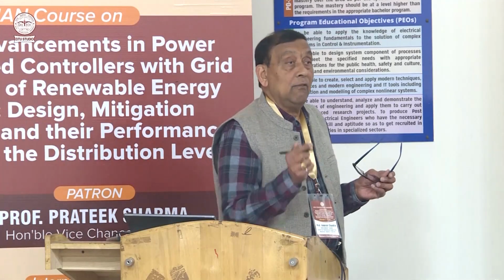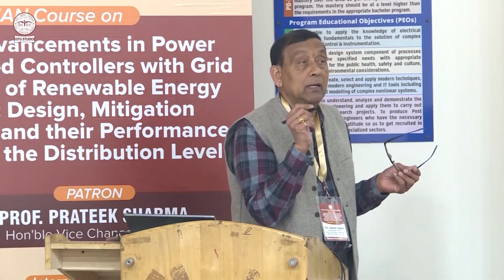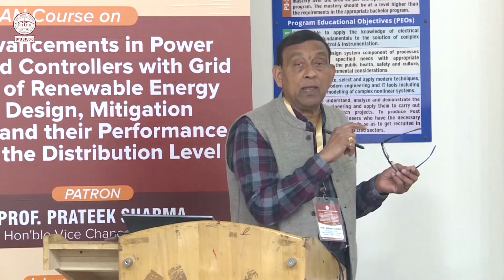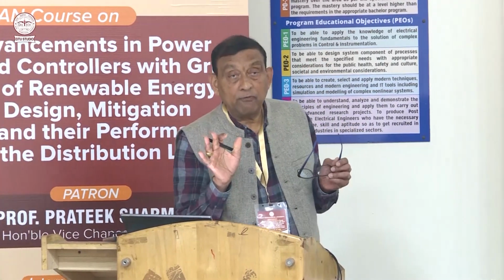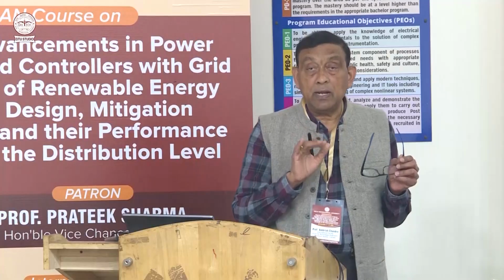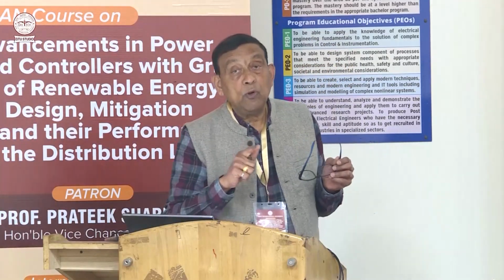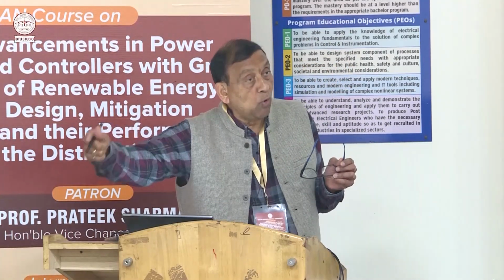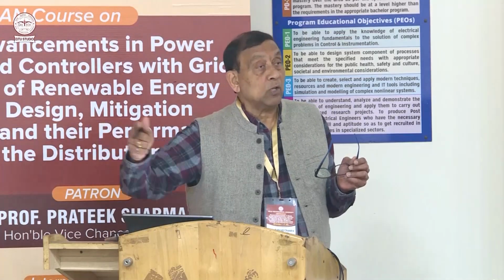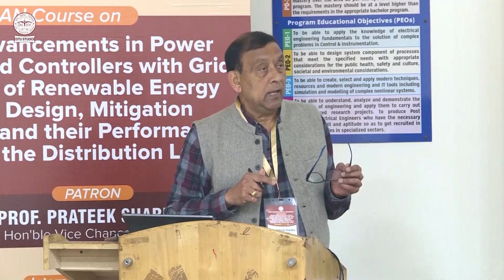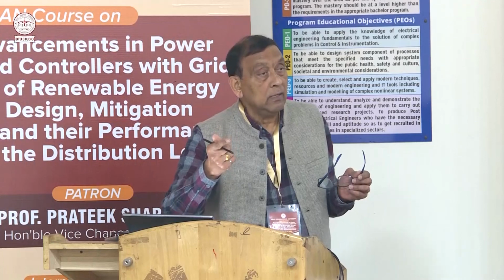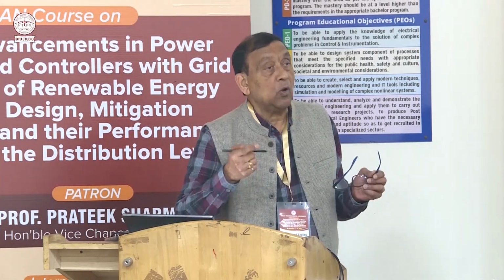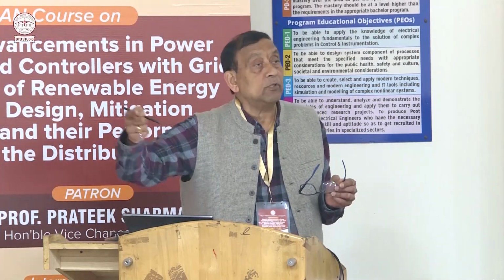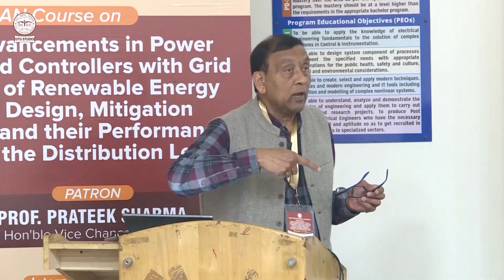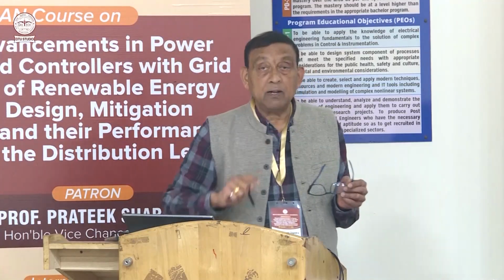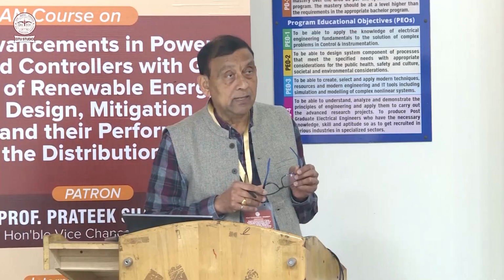So it means whatever eddy current losses you are having with the fundamental frequency, you will have 25 times more eddy current losses if you have a fifth harmonic. And if you have a seventh harmonic, then the eddy current losses will be 49 times more than what you are having at the fundamental frequency.